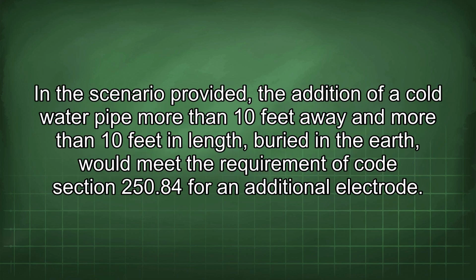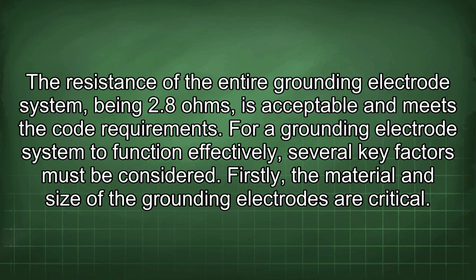In the scenario provided, the addition of a cold water pipe more than 10 feet away and more than 10 feet in length, buried in the earth, would meet the requirement of code section 250.84 for an additional electrode. The resistance of the entire grounding electrode system, being 2.8 ohms, is acceptable and meets the code requirements.